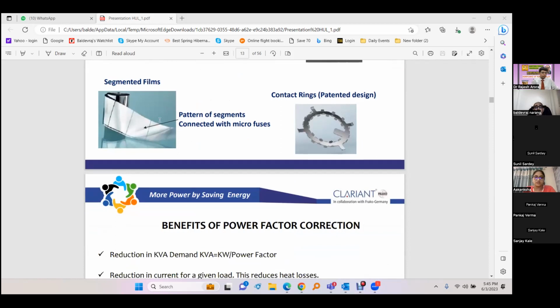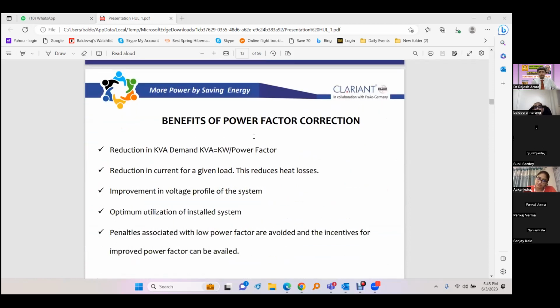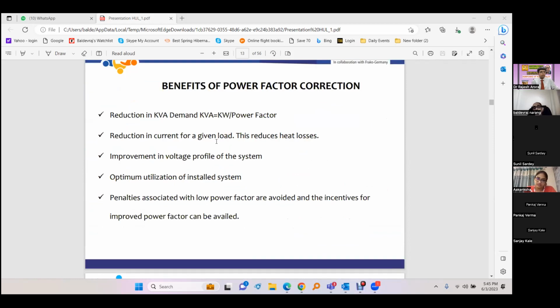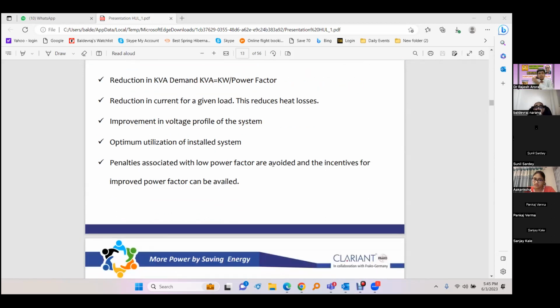Then power factor correction, we have these advantages. The KVA demand is reduced. The currents are less. We handle lesser current. Suppose we have a power factor of 0.9 going to unity, there is a 10% current reduction in that. Similarly, the demand also reduces in the same proportion. The voltage profile improves when the capacitors are there. The voltage profile is more stable. The voltage is better. Then the system installed capacity is fully utilized. When most of the industry is running at unity power factor, the systems on the utility side, the distribution side, are able to utilize their full capacity. And then all the penalties which come by way of poor power factor are removed if we have a good power factor.